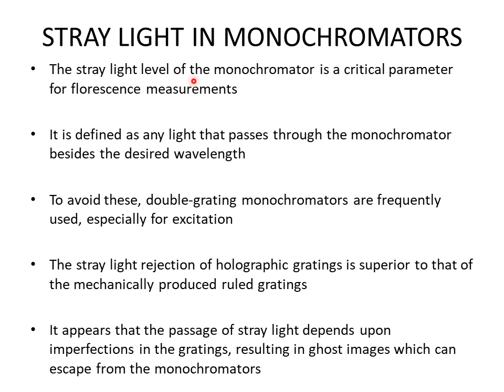Now we'll look at stray light in monochromators. The stray light level of the monochromator is a critical parameter for fluorescence measurement — the quality of fluorescence results is very much dependent upon it, which in turn depends on the quality of the monochromator. Stray light is defined as any light that passes through the monochromator besides the desired wavelength.